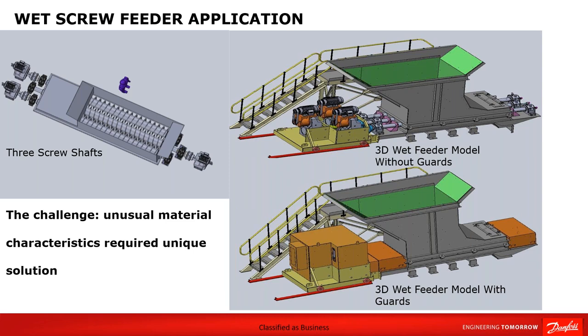So the higher the PPR, in other words the pulses per revolution, the better the sync. As the increments are closer to each other, this increases the resolution of the feedback. So in this application, we used 8192 PPR multi-turn absolute encoders. And when the wet feeder needs to run, it gives a start command to the master variable speed drive via its Profibus comms, and the master VSD then gives the start signals to the follower variable speed drives.